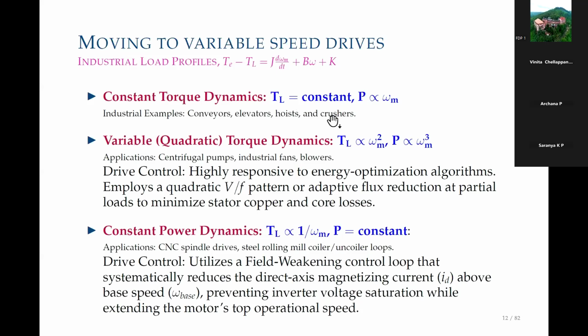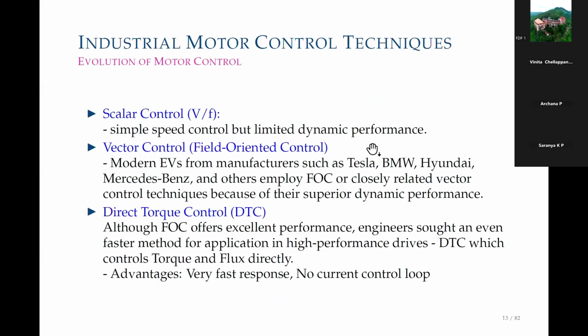Based on these load applications, we have to decide what control to keep. So we have to set the load profile of the system before working with it. These are some of the control techniques that we all know. One is the scalar control, which is open loop control, the V by F control, which we generally use for induction motors. Then we have the closed loop control, which is vector control, and the direct torque control.